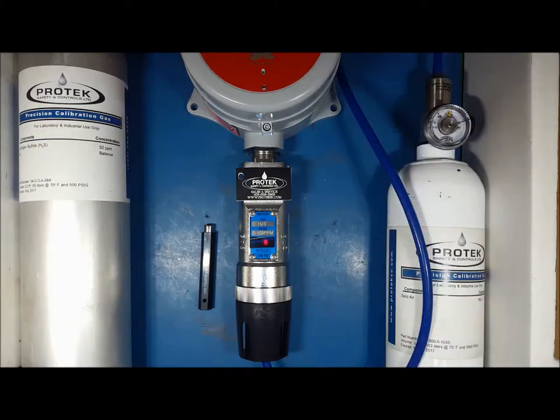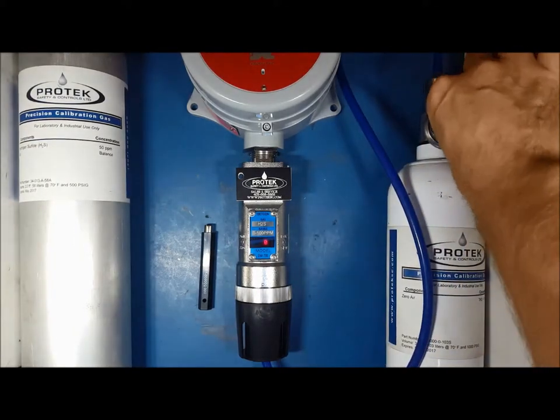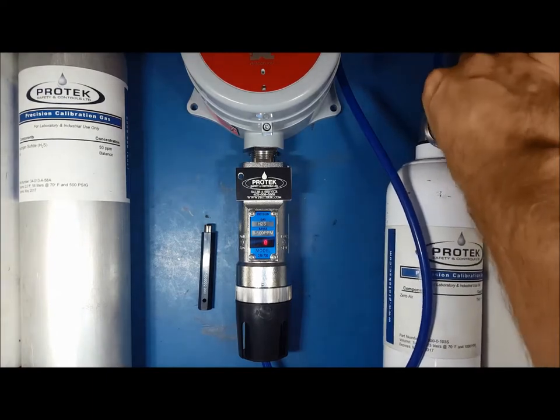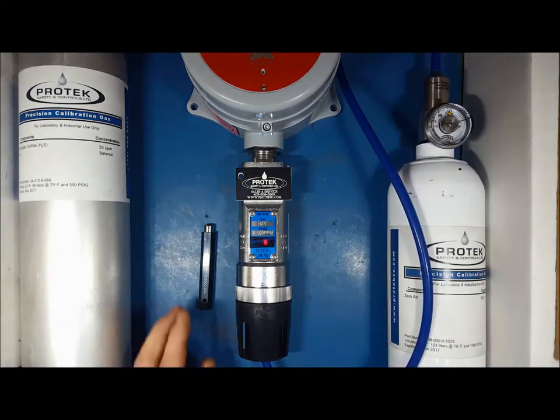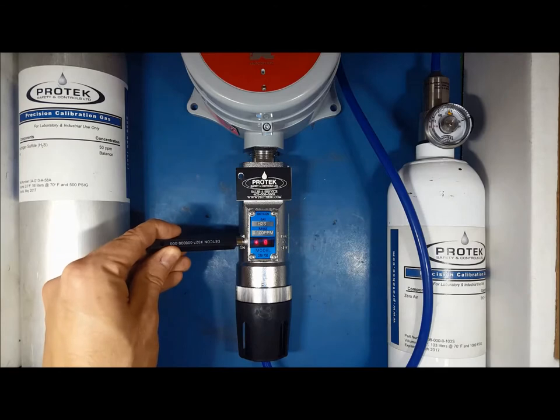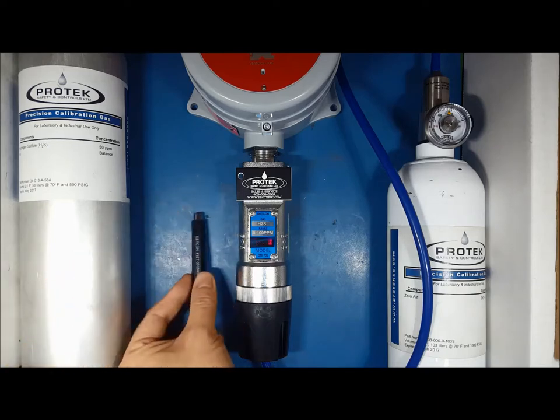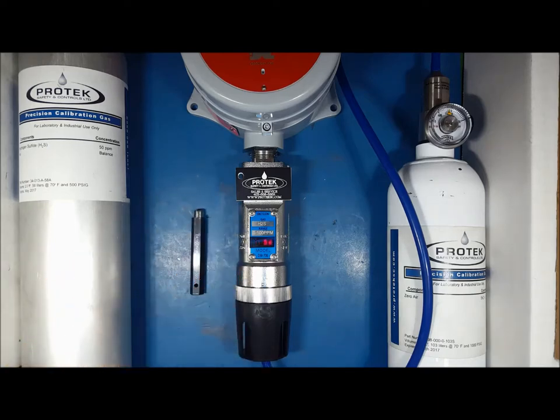While in operational mode, apply the zero gas to the sensor element. Hold the magnet over PGM1 to bring up the calibration menu. From there, hold the magnet over PGM1 for another 5 seconds. The display will state 0 cal twice across the screen. At this point, the magnet can be removed from the transmitter. It will then scroll setting 0 twice. Once it is finished, it will finally state 0 saved across the screen twice. After this, the unit will go back into operational mode.